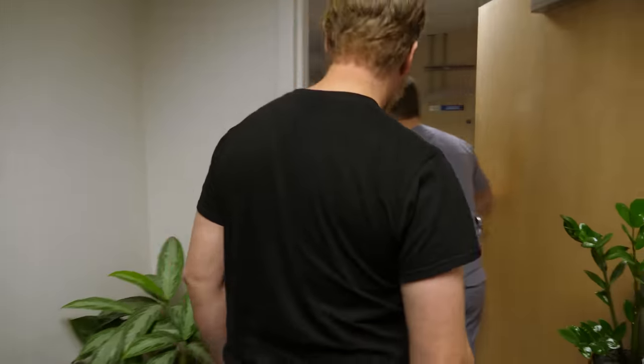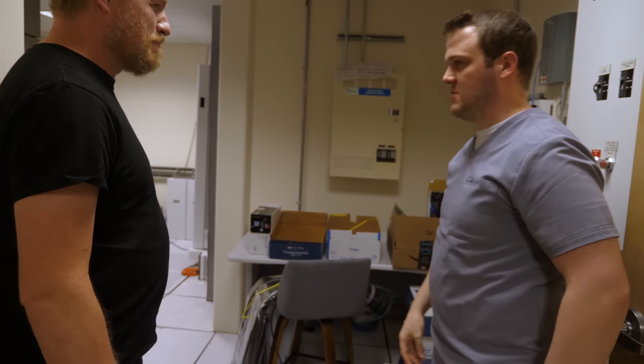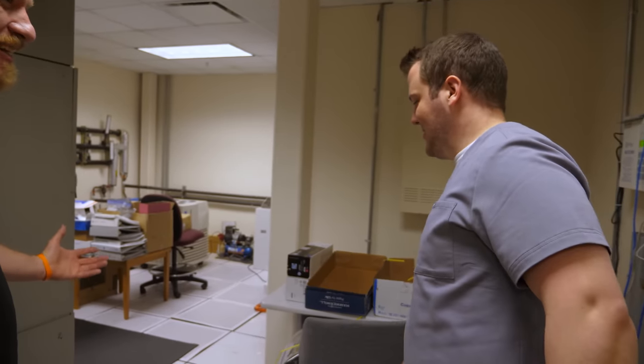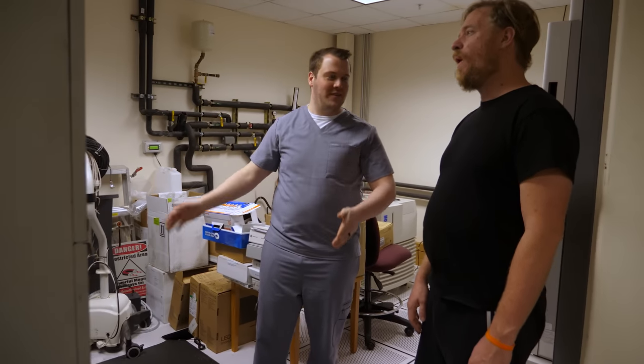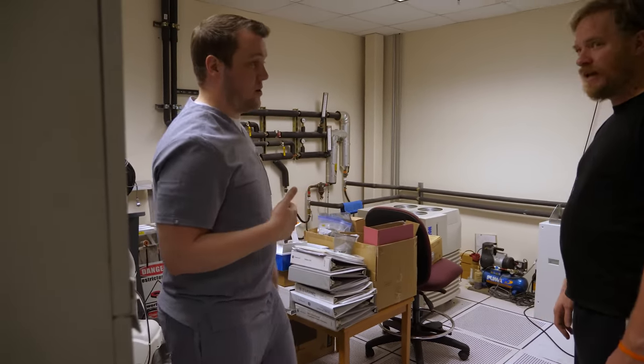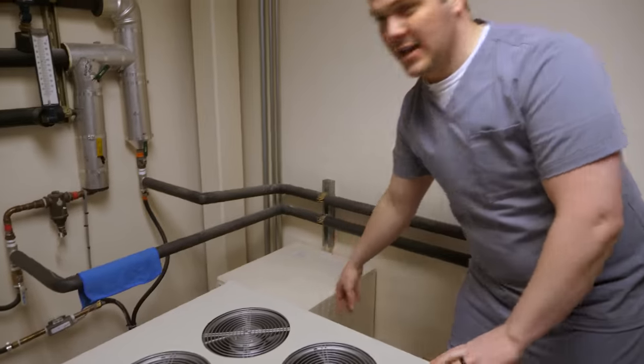Back in the day this server room was totally full of computers — Moore's law in action. Now we have just this: the actual MRI computer, which brings in all that signal, analyzes it, and spits out the images. It shrank from the size of a small room to this. This one is part of our helium circulator — the helium is in liquid form circulating in the magnet to keep it cold while running, which helps maintain the electrical circuitry of the electromagnet.